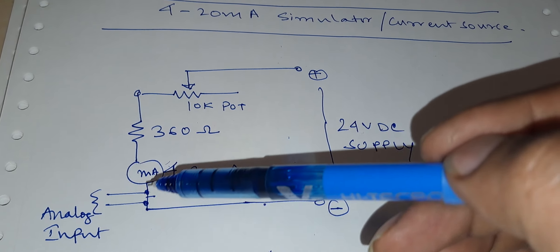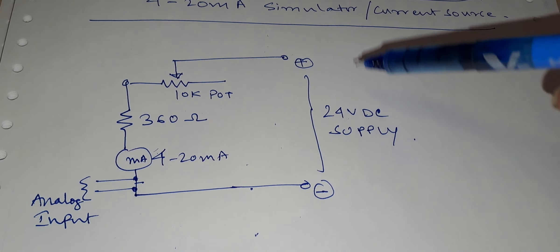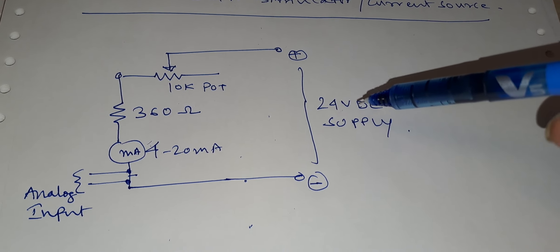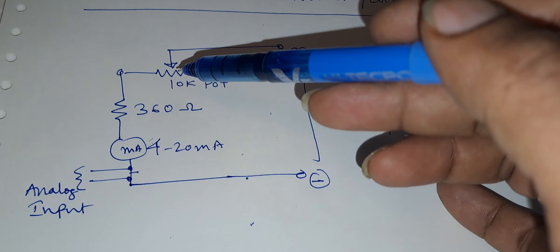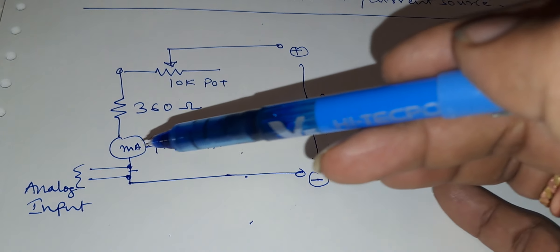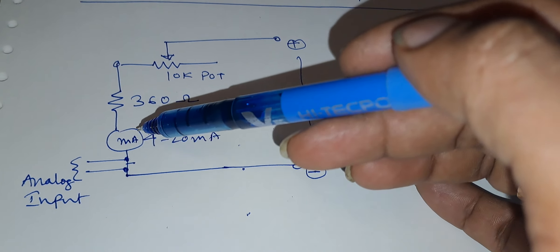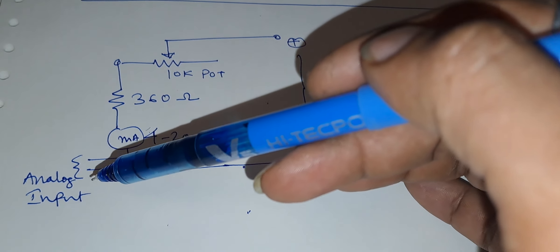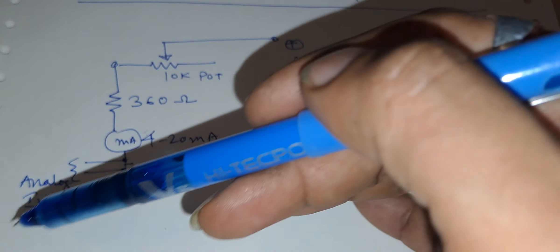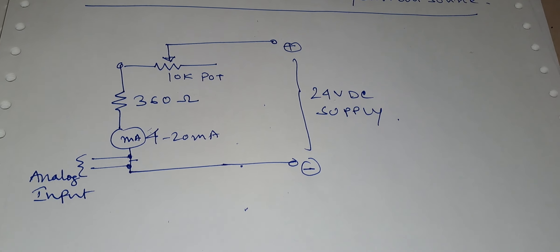This is the basic circuit diagram. Here is the 24 volt DC supply, and when we adjust the potentiometer knob there will be a current change from 4 to 20 mA across the mA meter. The same current will be reflected in the analog input card and it will show us the scaling of the card. This is a very basic and simple circuit to implement.